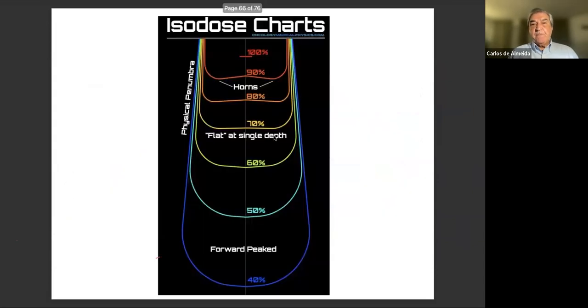Next slide. In the depth dose curves it is even more critical, because this is the data that you enter into the treatment planning system to do the dose calculation for the patients. And you must have a detector able to see the difference here, on this physical penumbra area. Normally you measure the flatness at different depths with the detector. So you enter this data in the treatment planning system because it's very difficult to identify just by looking at this number and this dimension. Next one.